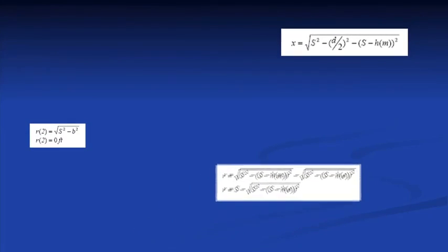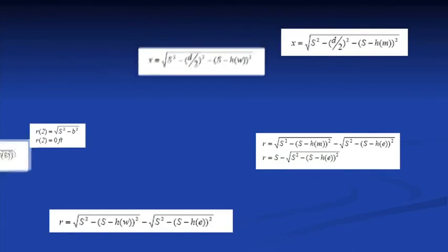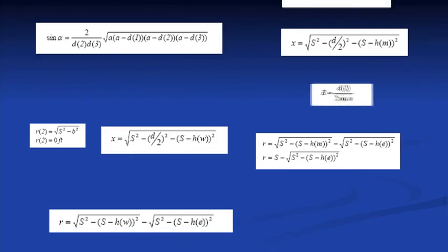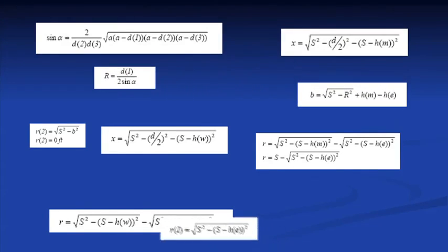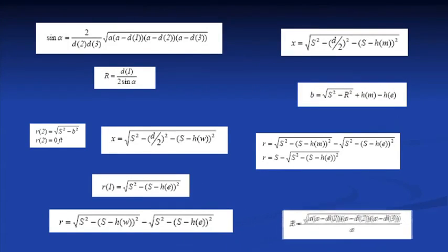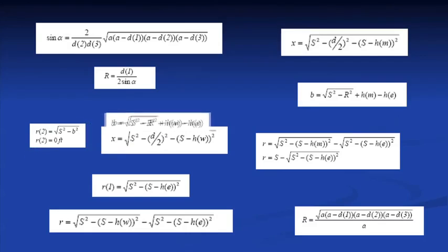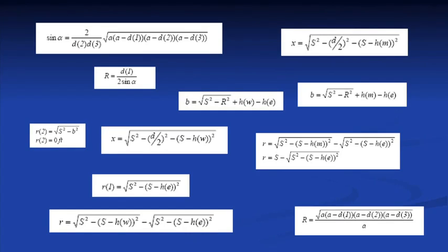Well, a gentleman by the name of Jeff Camden wrote a paper a few years back, and he figured out the geometries for us, and he came out with some geometric formulas for some very common configurations. So rather than just knowing S and rolling the sphere around to test everything, you can actually calculate the protection zones provided by your masts and wires with his formulas.